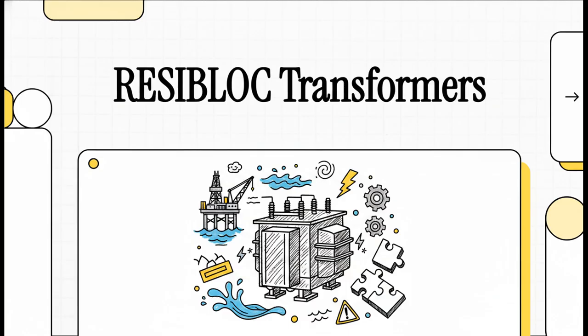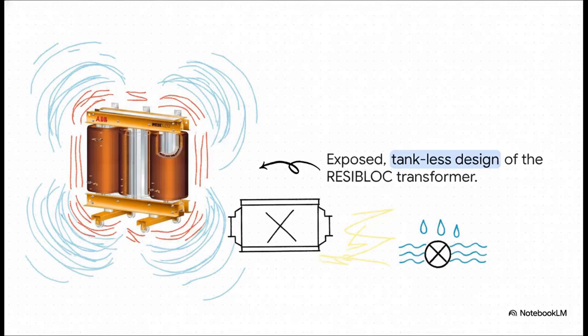We're going to see exactly why this is considered the ultimate engineering solution for tight offshore electrical rooms and why understanding its mechanics is an absolute must for any rigorous commissioning process. Now take a look at this. What you don't see in this design is just as important as what you do see. Notice how this transformer just sits entirely in the open air? There's no heavy protective metal tank built around it, and there's definitely no complex fire suppression system enveloping the unit. It's completely exposed. And no, that isn't some cheap cost-cutting measure.